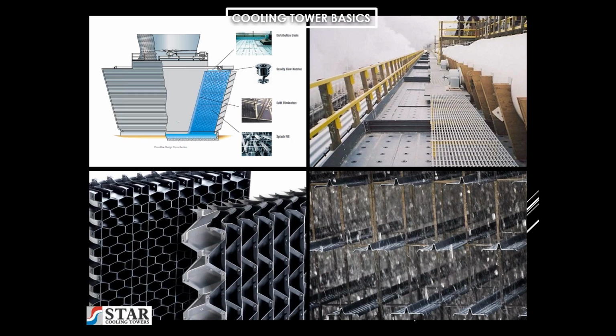We look at the cross-flow cooling tower. The hot water is returned through a large distribution header pipe and is discharged through a flow control valve, which is designed to throttle the water to even the levels in each independent basin. Below the valve is a splash box that incorporates baffles to take the energy out of the water, allowing the water to be still in the basin. And in the basin floor is a series of gravity flow nozzles that are typically spaced 12 inches by 12 inches that distributes the water evenly and equally over the fill.